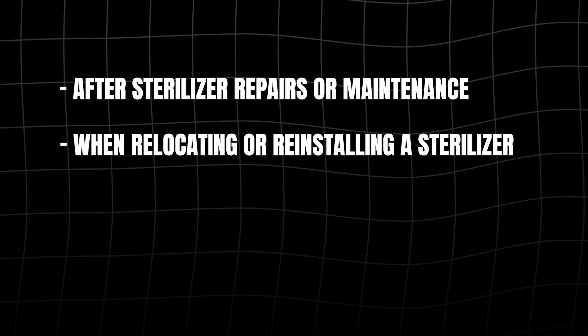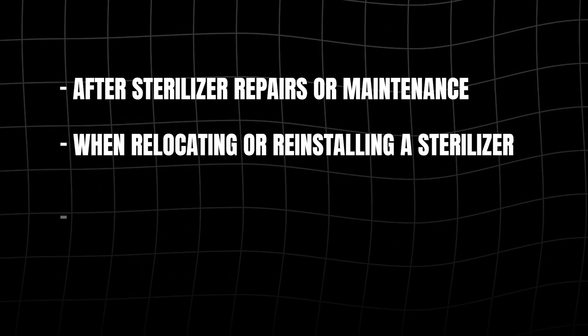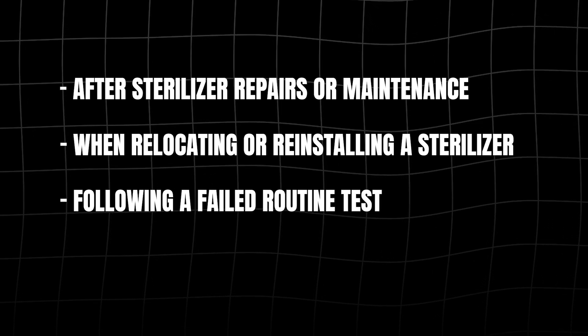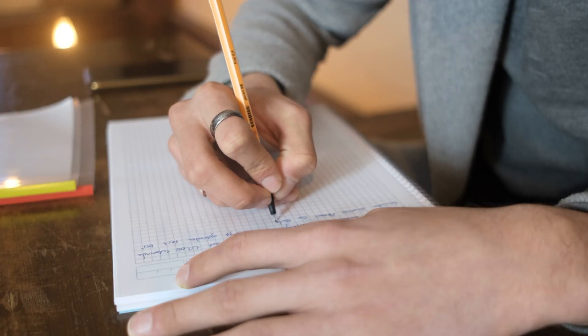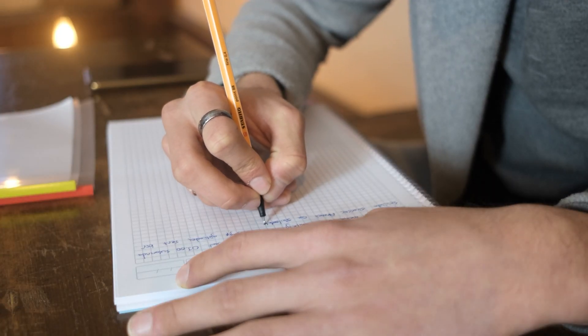Now let's talk about situations that call for testing outside of normal operations. These can include instances like after sterilizer repairs or maintenance, when relocating or reinstalling a sterilizer, following a failed routine test, and after significant downtime or power outages. In these cases, you'll want to repeat all three tests — leak, air removal, and biological. Always document your results and communicate any issues promptly.